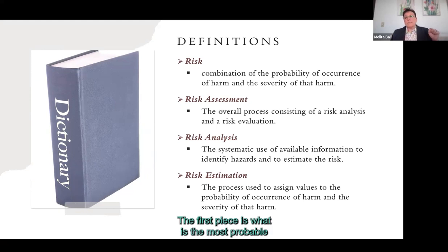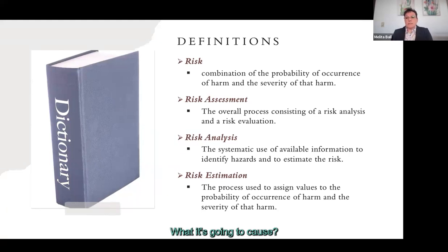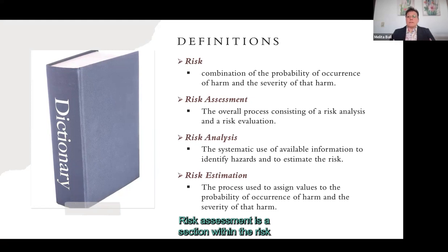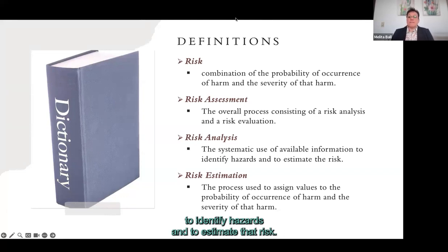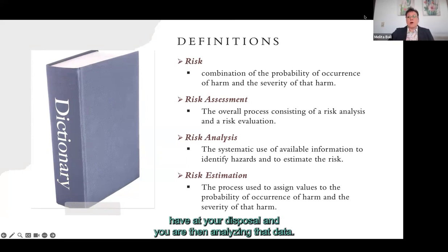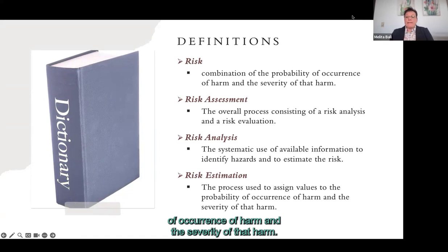There are two key litmus tests: what is the most probable area of occurrence for a particular harm, and if it were to occur, what will the severity be — will it be a minor injury, death, or anything in between? Risk assessment covers two things: risk analysis, which is the systematic use of available information to identify hazards and estimate risk; and risk estimation, which is the process of assigning values for probability of occurrence and severity of harm.